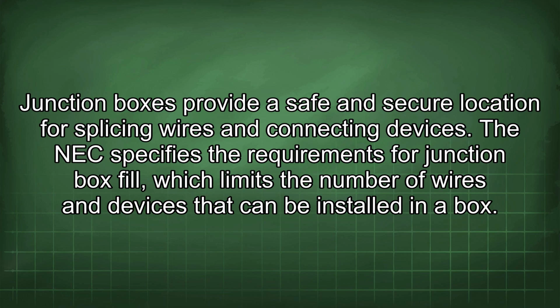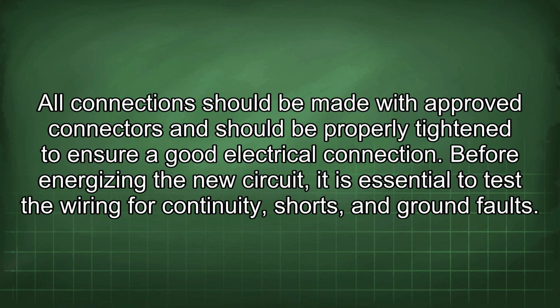The NEC specifies the requirements for junction box fill, which limits the number of wires and devices that can be installed in a box. All connections should be made with approved connectors and should be properly tightened to ensure a good electrical connection. Before energizing the new circuit, it is essential to test the wiring for continuity, shorts, and ground faults.